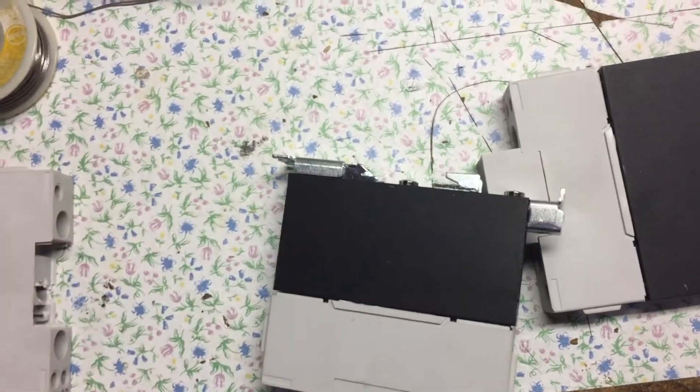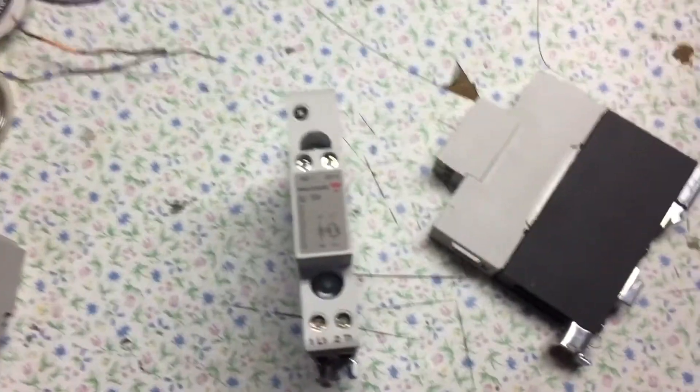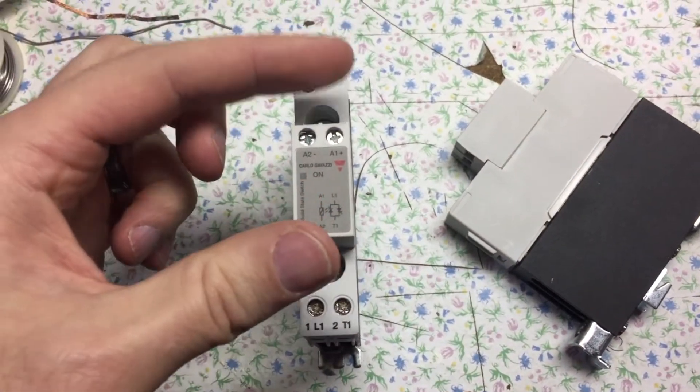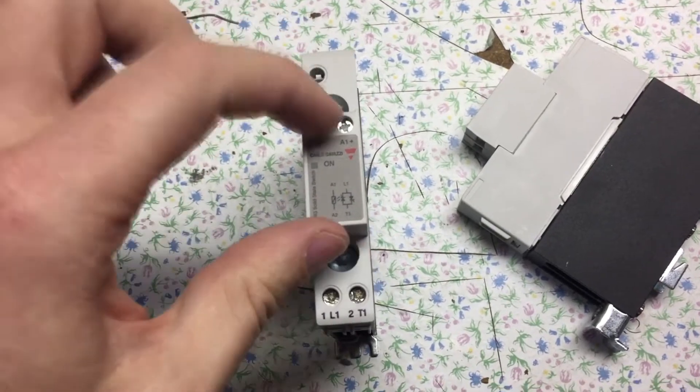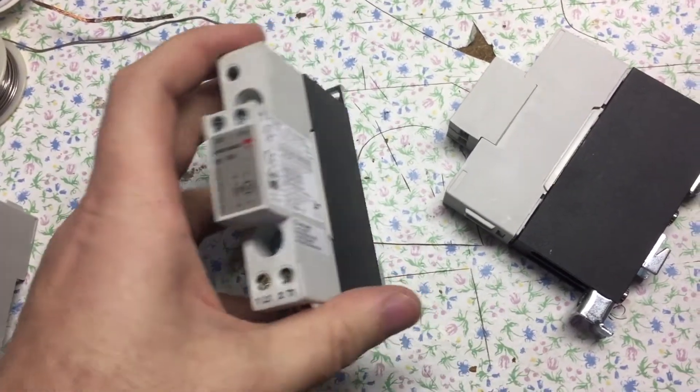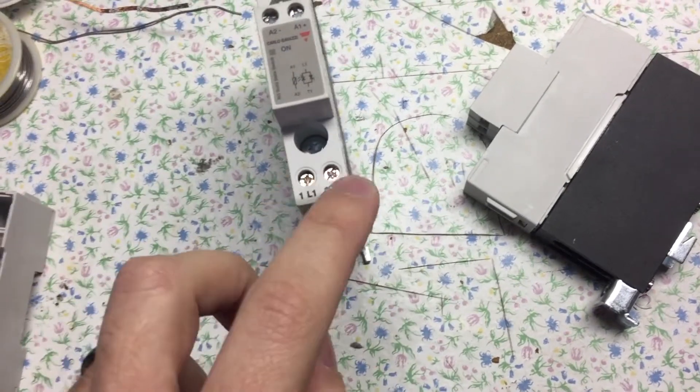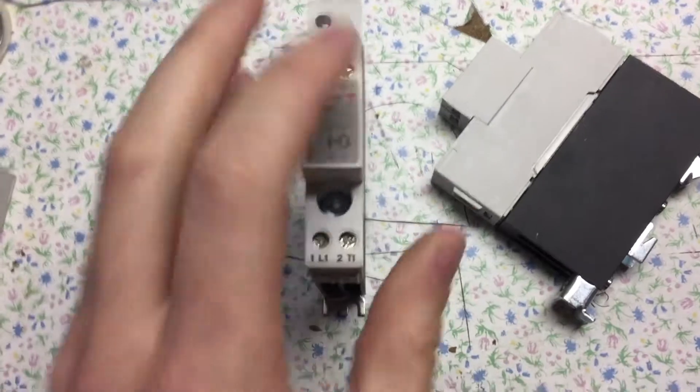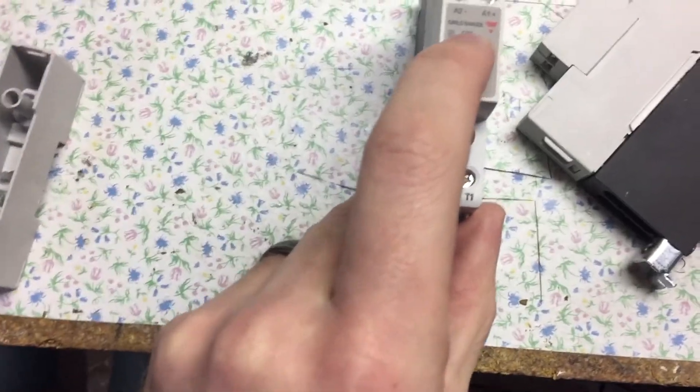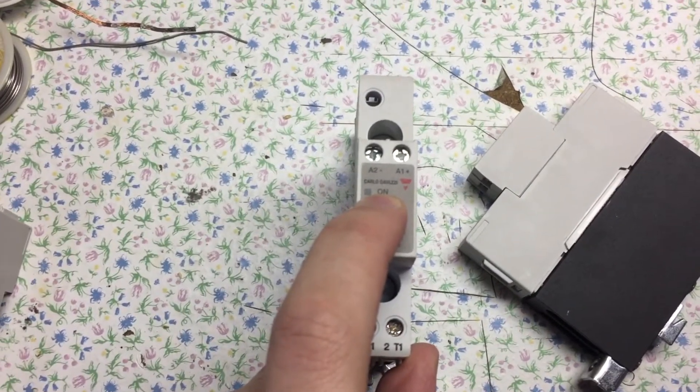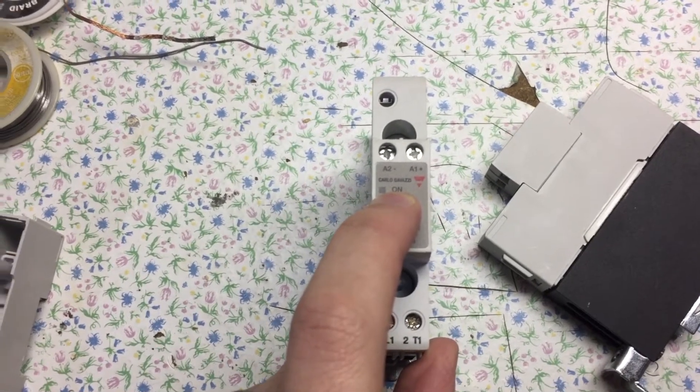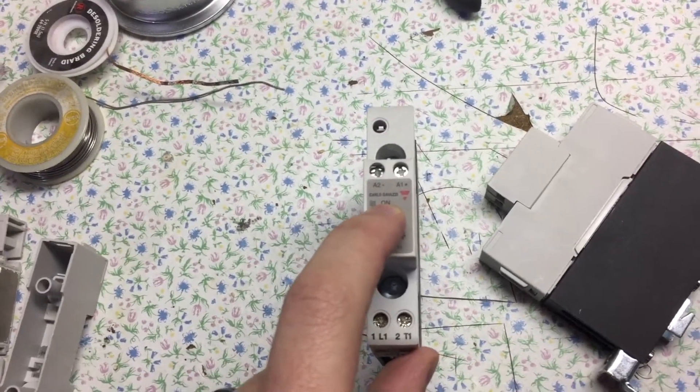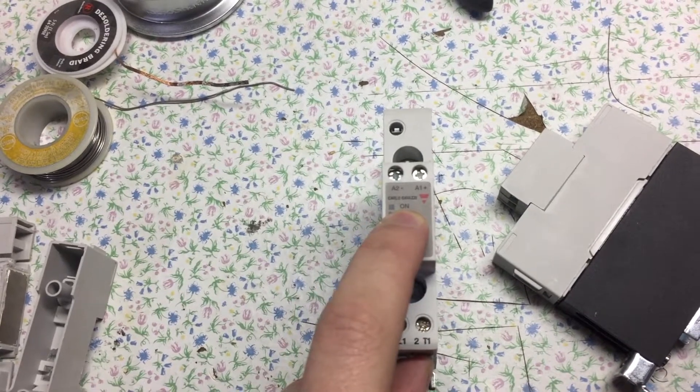As I was mentioning before, the signal from the brain or the PLC comes in here. That tells the relay to allow the high current over here on these terminals to pass through and go to the heaters. There's a little light that lights up right there when it's activated and gets a signal from the PLC. These weren't lighting up or not lighting up consistently, so there was a problem there.